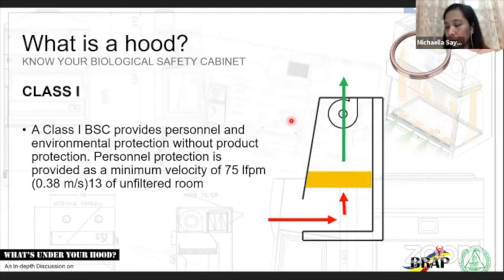So you have your class 1. Class 1 provides personal and environmental protection without product protection. So this is your airflow. All the air comes in. If, for example, your product is in right here, imagine if your environment is dirty, all the dirty air passes through your product before it is filtered out and blown by your blower outside. So for class 1, you only have one HEPA filter. It's between the product and the exhaust blower. So this is one of the principles in using your biosafety cabinet. Your blower here creates a vacuum in this space, which sucks in air from this portion.